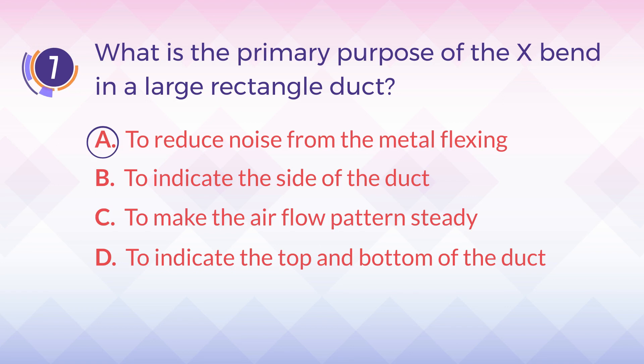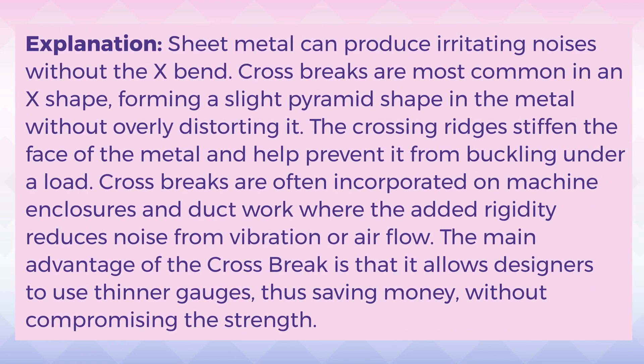The answer is A. To reduce noise from the metal flexing. Explanation: Sheet metal can produce irritating noises without the X-Bend. Cross breaks are most common in an X-shape, forming a slight pyramid shape in the metal without overly distorting it. The crossing ridges stiffen the face of the metal and help prevent it from buckling under a load. Cross breaks are often incorporated on machine enclosures and duct work, where the added rigidity reduces noise from vibration or airflow. The main advantage of the cross break is that it allows designers to use thinner gauges, thus saving money, without compromising the strength.